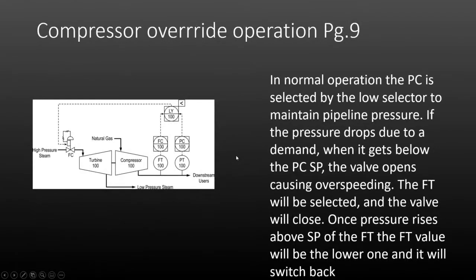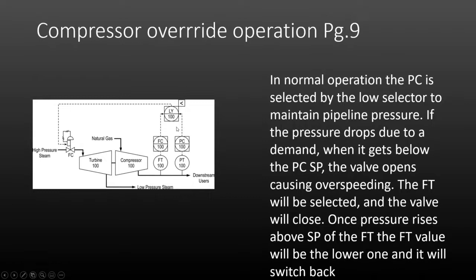Here we have a compressor with an override strategy — flow and pressure are measured on the output of the compressor, and we have a low selector. Almost all applications covered today — nine out of ten — are going to be low select. The reactor temperature example is the only one in the entire ILM that uses a high selector. In normal operation, the pressure controller is selected by the low selector in order to maintain the pipeline pressure.